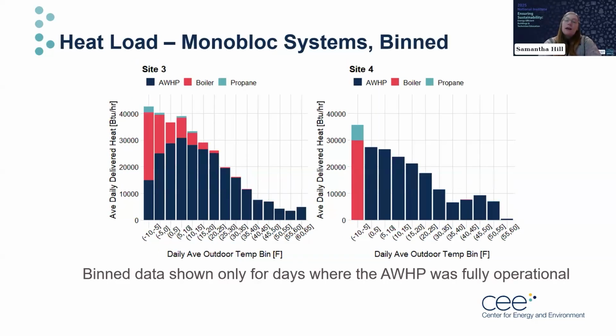And here's how much load was delivered by our monoblock systems, site 3 and site 4. Again, here, these controls are a little bit more complex and sophisticated, so we see a lot less boiler usage in mild temperatures, and we again see the majority of the heat is delivered successfully by the air-to-water heat pump, and it's only in the very coldest weather, below -5 degrees Fahrenheit, where the boiler has to take up the majority of the heating load. Though these particular units could operate as cold as -13 degrees Fahrenheit.